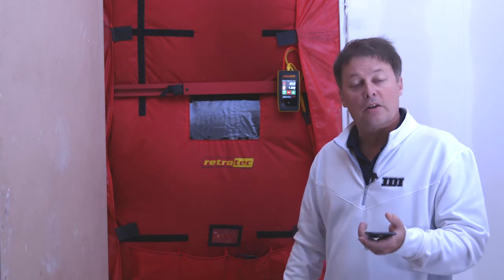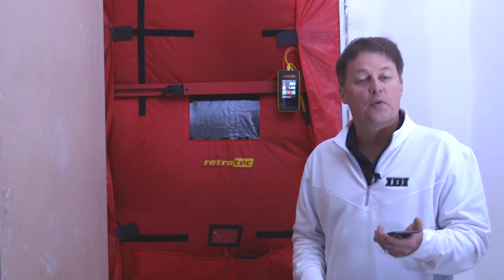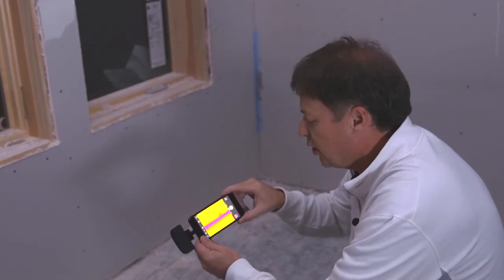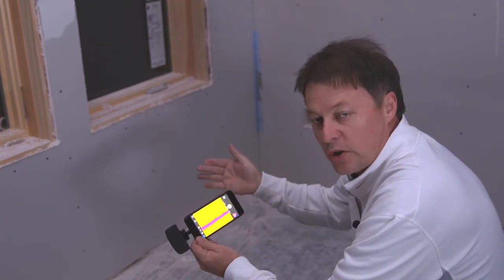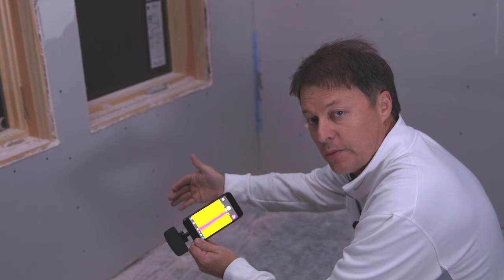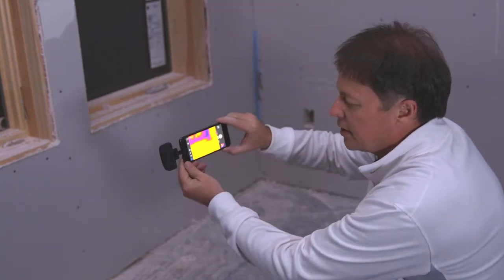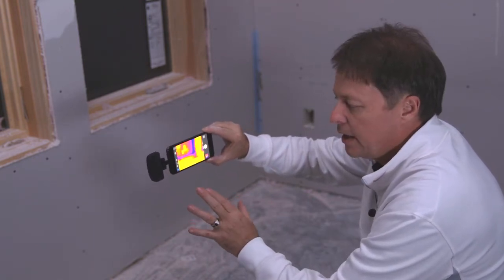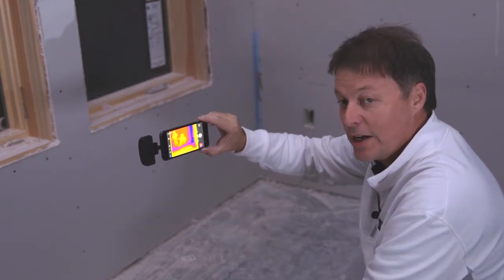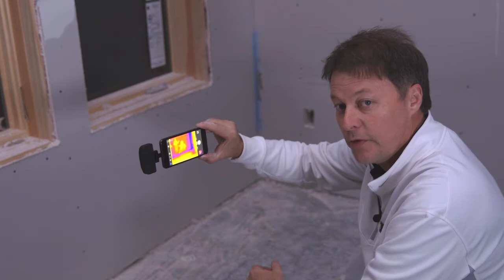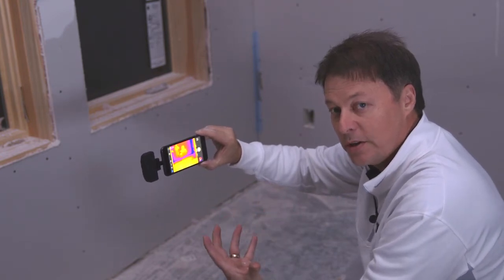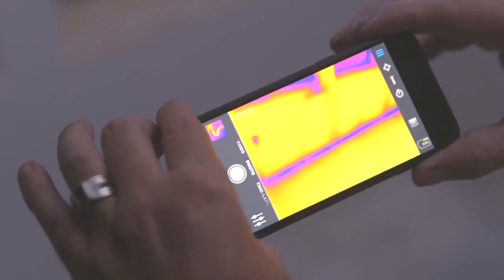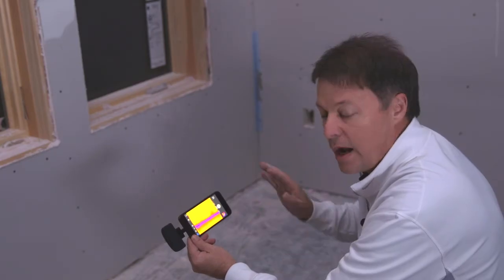I'm going to go around the house, leave the blower door running, turn on my infrared camera, and we're going to see what kind of job we did. We've been around the house and what we're looking at now is where the two slabs meet — the slab and the foundation meeting at the footings. When we look at this camera and we see the windows, obviously the windows don't have a whole lot of R-value. But I can see my reflection in the window — there's that much heat coming off of me. As we look down at the floor, we can see where those two slabs connect. That tells us our camera's working beautifully.